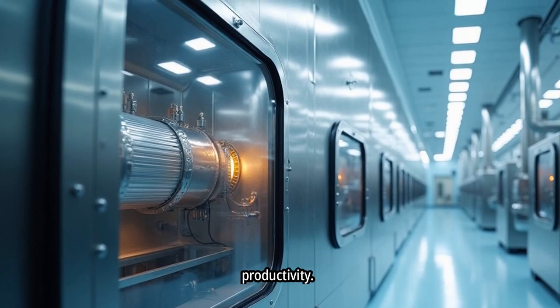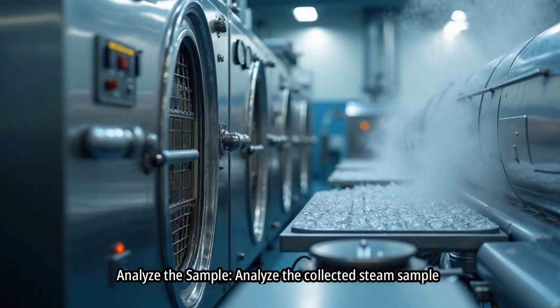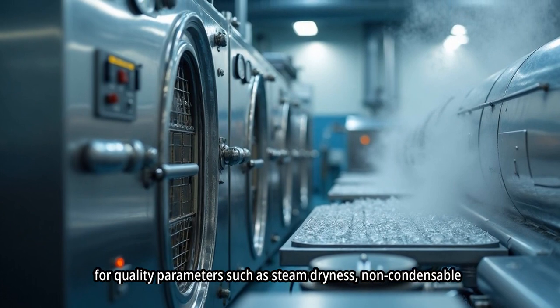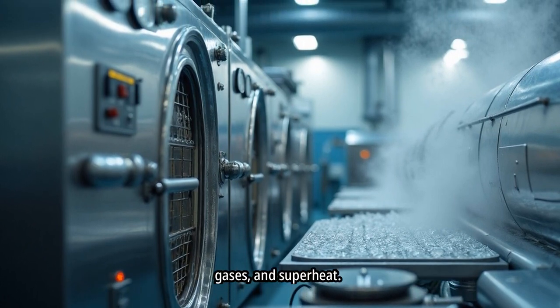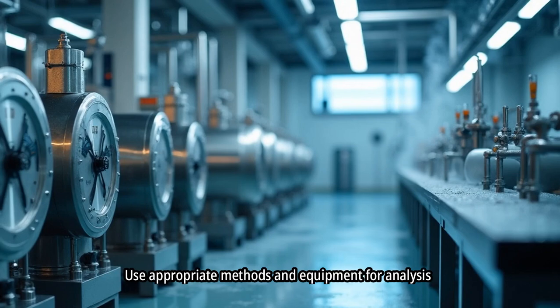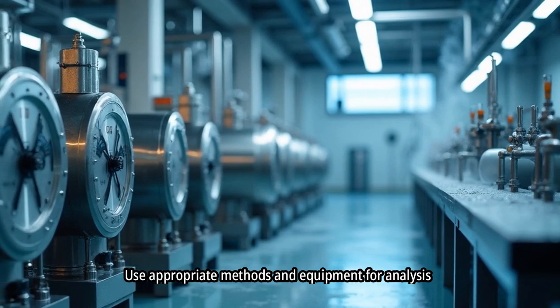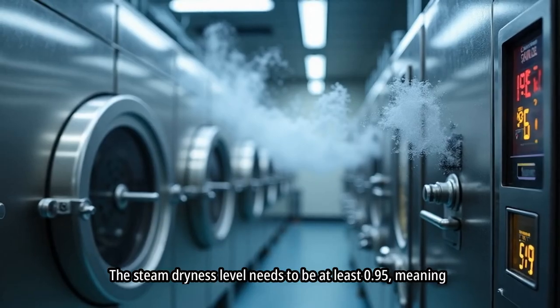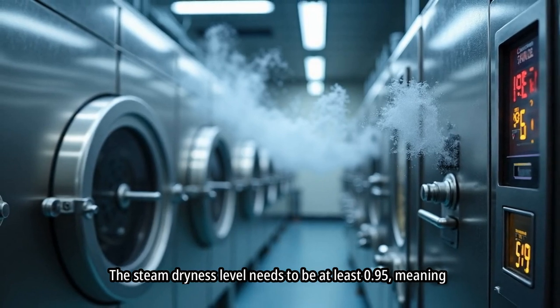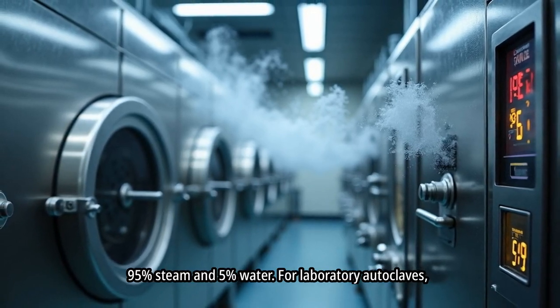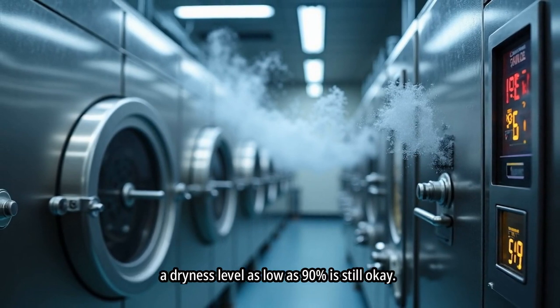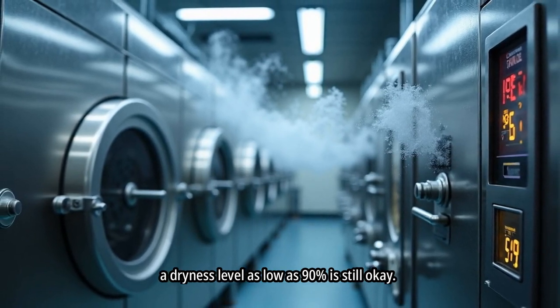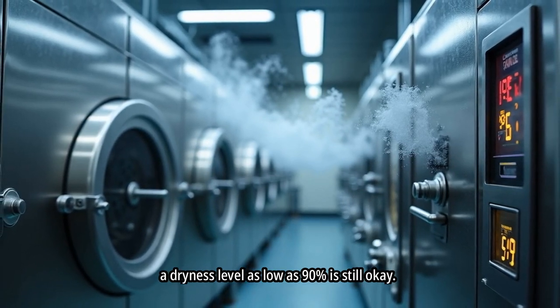Analyze the sample. Analyze the collected steam sample for quality parameters such as steam dryness, non-condensable gases, and superheat. Use appropriate methods and equipment for analysis. The steam dryness level needs to be at least 0.95, meaning 95% steam and 5% water. For laboratory autoclaves, a dryness level as low as 90% is still okay.